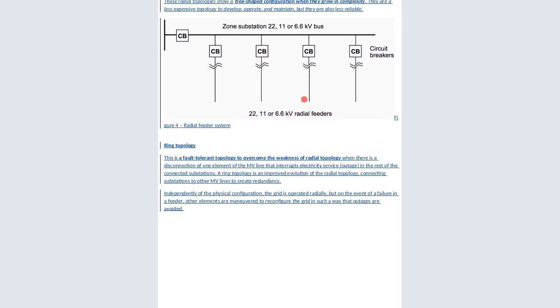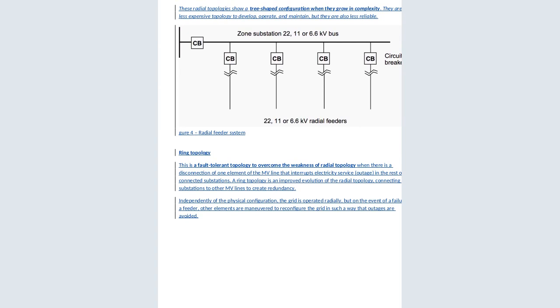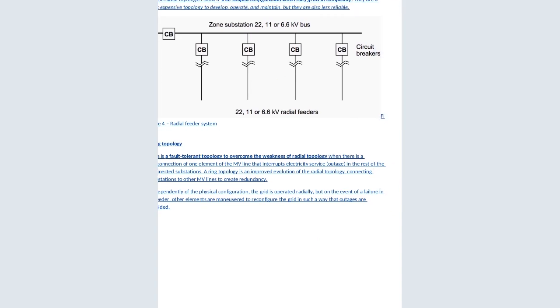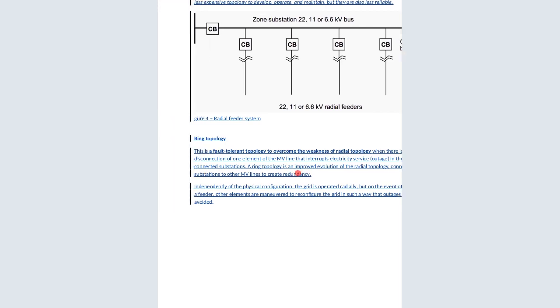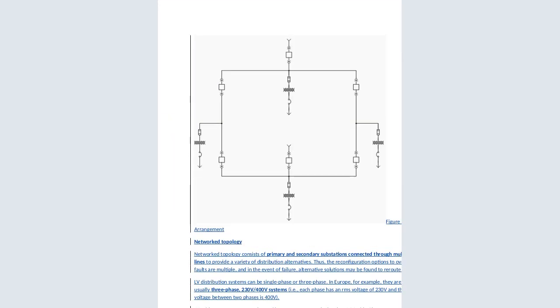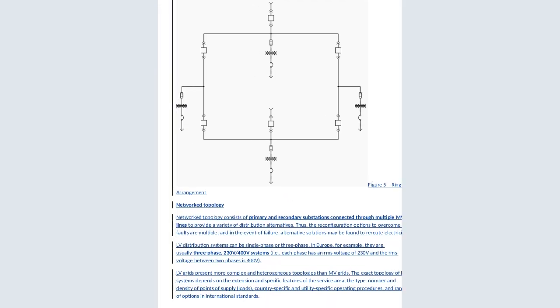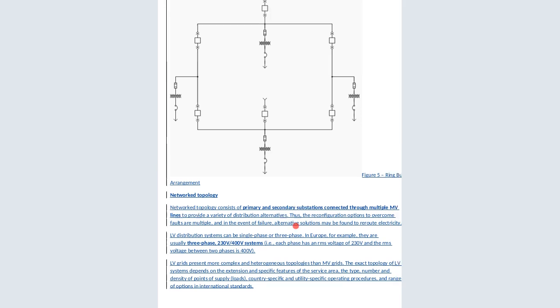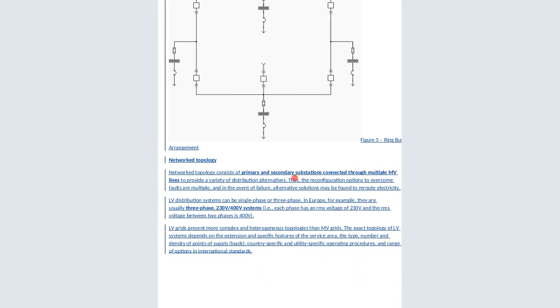We realize that with this kind of topology, which is the radial, once one circuit breaker is affected like this, it will have to cut the supply for the rest of the subsequent feeders, which is a shortfall. So the ring topology comes in to solve that problem of the radial topology. So you can now see how the ring happens. It means that each breaker, these are the breakers, they are tapping from the main. You can see this is a transformer supplying, and this is another one, and this is another one. So this one is independent of this, and they are parallel to each other. So the arrangement, now you can see, is the ring bus.